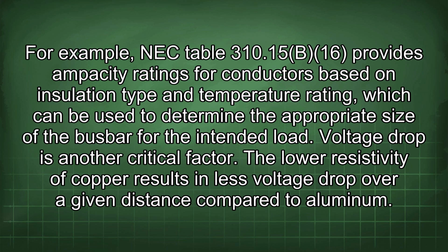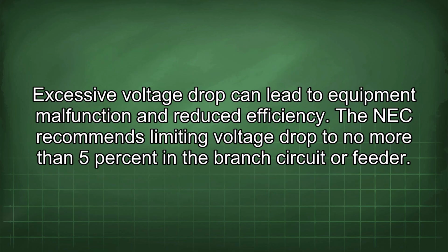Voltage drop is another critical factor. The lower resistivity of copper results in less voltage drop over a given distance compared to aluminum. Excessive voltage drop can lead to equipment malfunction and reduced efficiency. The NEC recommends limiting voltage drop to no more than 5% in the branch circuit or feeder.